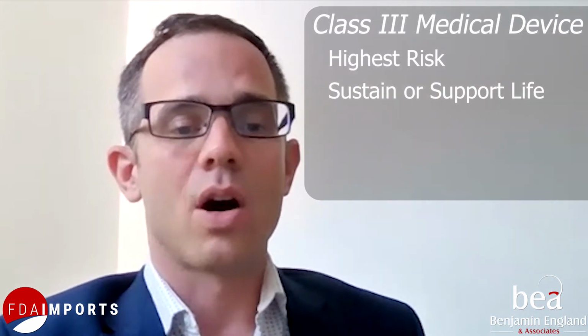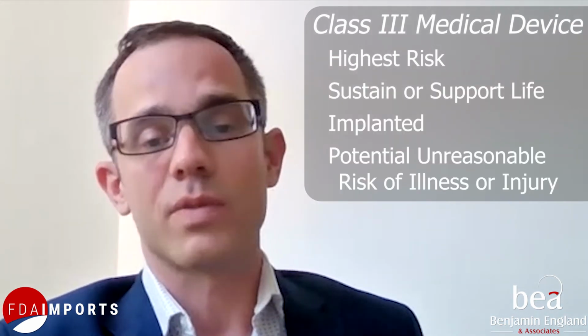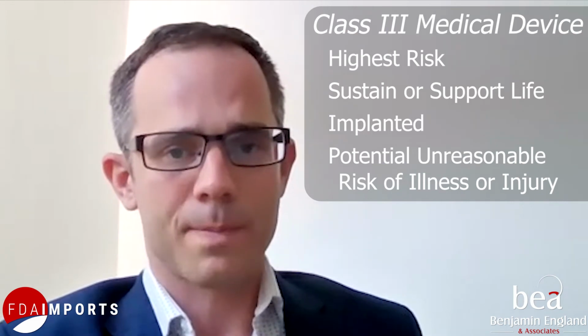Class 3 devices represent the highest risk to consumers and are usually devices that sustain or support life, are implanted, or present potential unreasonable risk of illness or injury. Manufacturers of Class 3 devices are required to submit a complete pre-market submission, also known as a PMA, which oftentimes includes clinical data. If you are a manufacturer of a medical device, determining the device's classification is an essential preliminary step in determining what laws apply and how to maintain compliance.